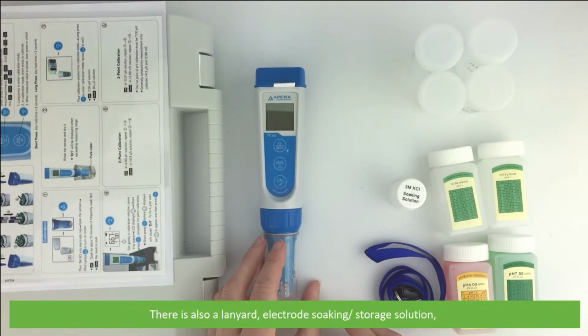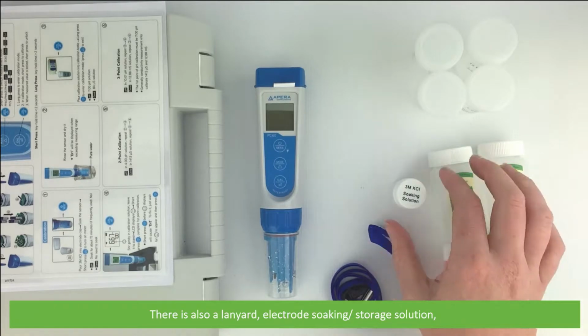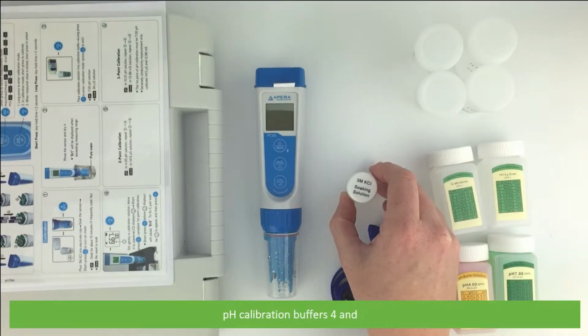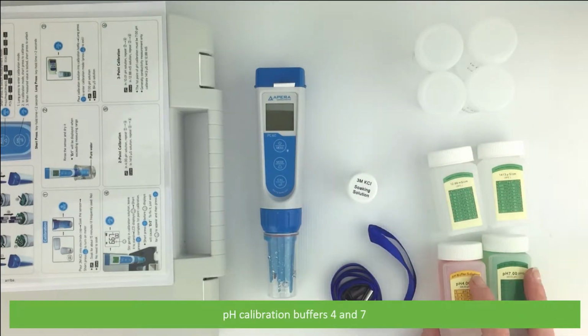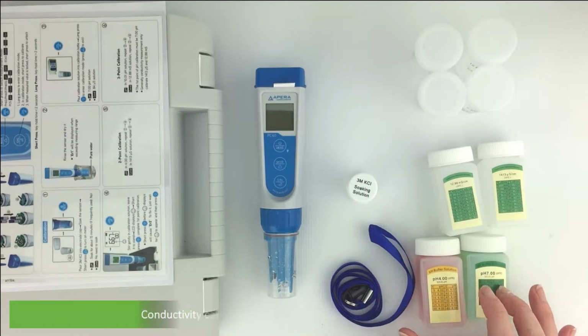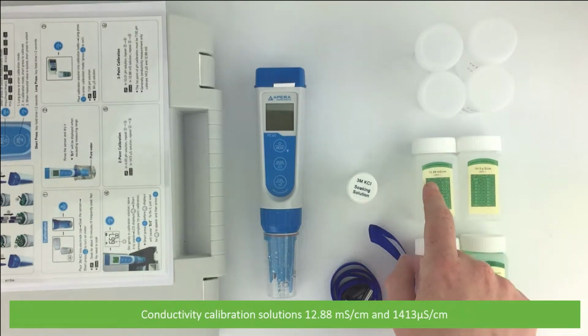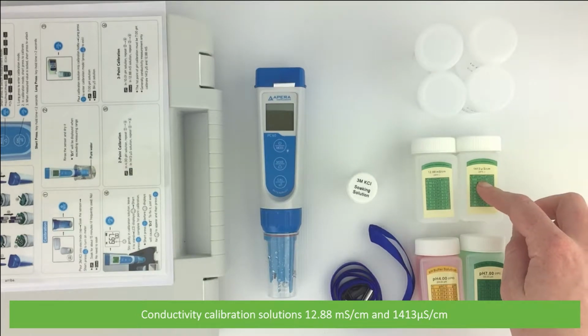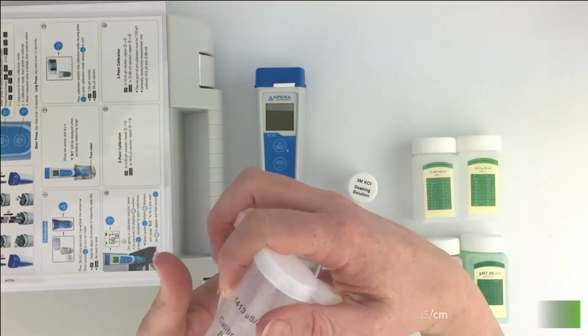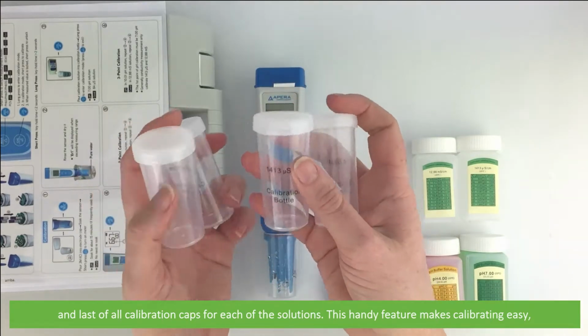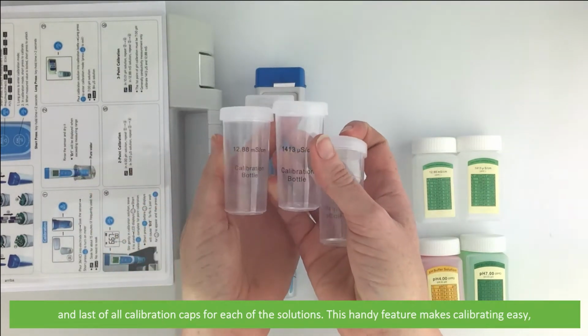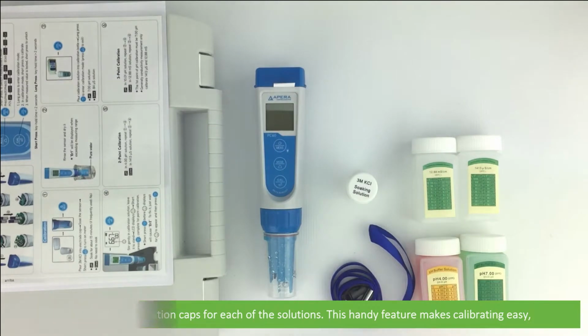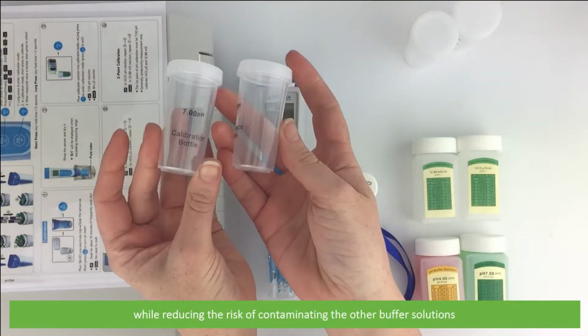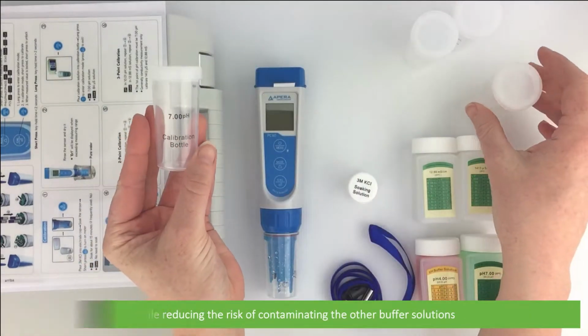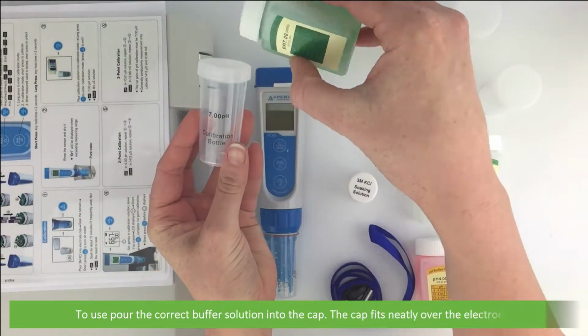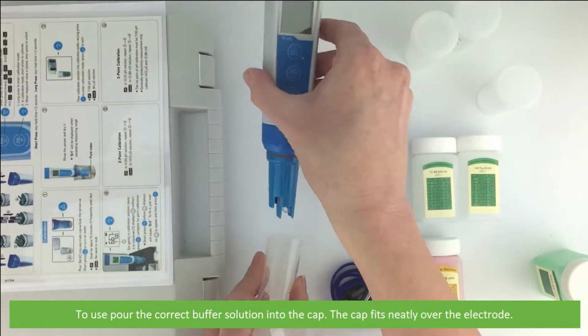There is also a lanyard, electrode storage solution, pH calibration buffers 4 and 7, conductivity calibration solutions 12.88 millisiemens per centimeter and 1413 microsiemens per centimeter. And last of all, there's calibration caps for each of the solutions. This is a handy feature that makes calibrating easy while reducing the risk of contaminating any buffer solutions. To use, pour the correct buffer solution into the cap, and the cap fits neatly over the electrode.